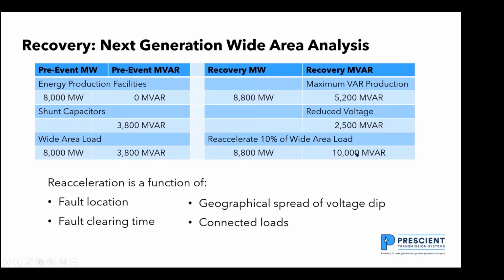So if the new MVAR demand is 10,000 and the capability is 7,700, this is the type of thing that leads to a wide area blackout, because I don't have enough MVAR to get all my machines reaccelerated. If the voltage dip persists too long, the auxiliary systems in the traditional power plants start tripping out on low voltage. And once I'm having trouble recovering and I trip my first power plant off, that's going to be a cascade.